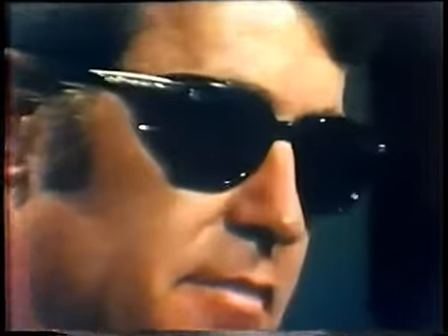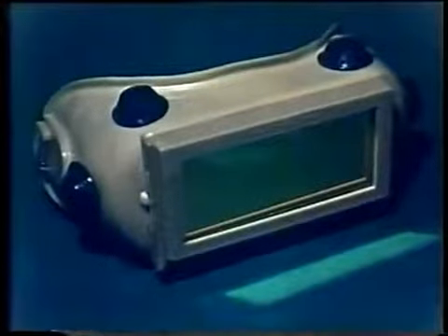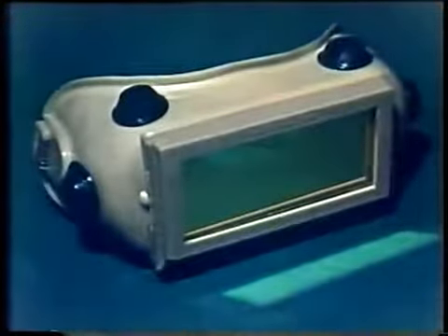Safety glasses should be worn at all times during laser operations. Since protective eyewear is available for different kinds of lasers, one must be certain that the glasses which are to be worn provide protection at the laser wavelength which is to be used. Wavelength must be noted on the glasses.